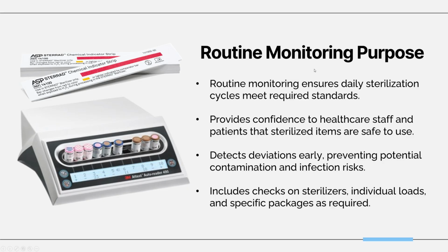So some routine monitoring is daily checks to ensure every cycle meets set parameters. So this includes reviewing physical printouts, verifying chemical indicators change colors, for example, and logging results in a tracking system. Routine monitoring helps catch issues early and supports patient safety and regulatory compliance.